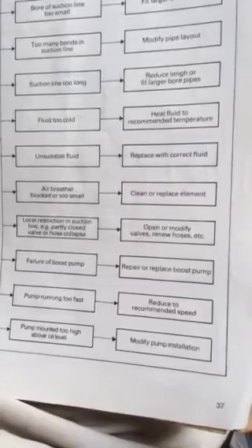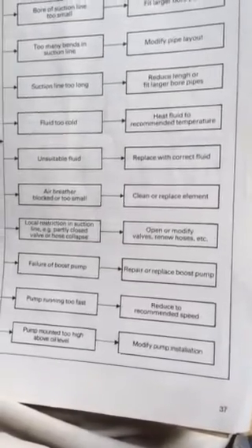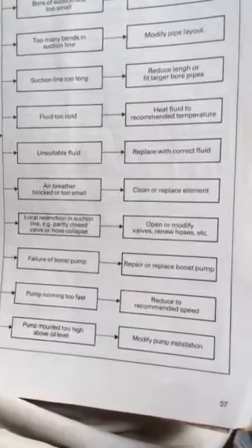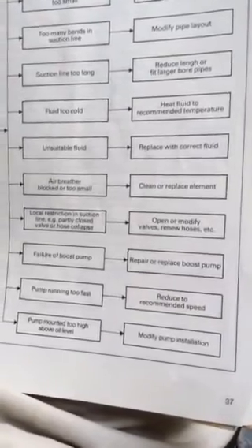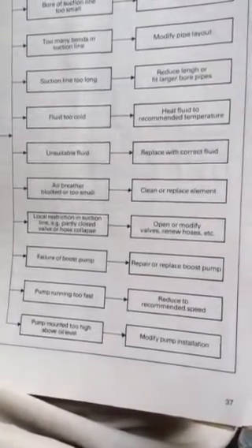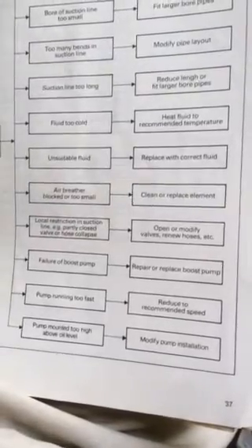Failure of boost pump, repair or replace boost pump. Pump running too fast, reduce to recommended speed. Pump mounted too high above oil level, modify pump installation.